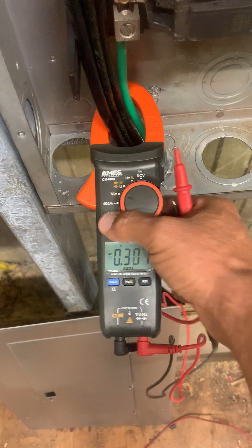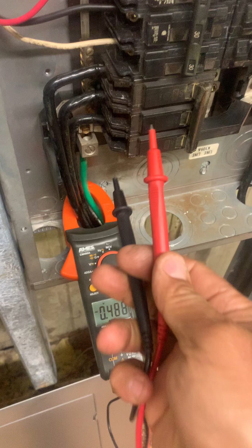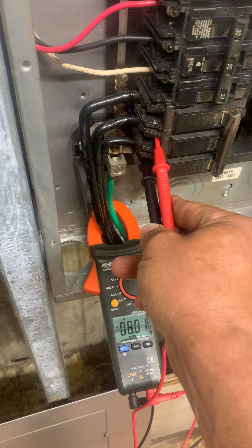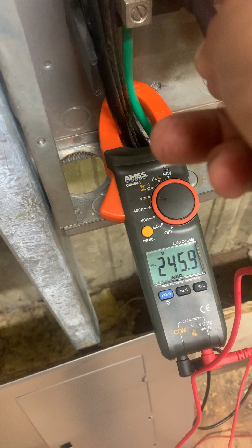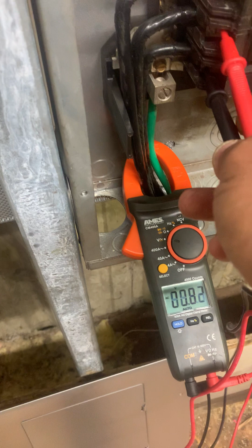I'm just gonna pinch in here, I'm doing nothing, just holding the meter. I'm gonna put it on voltage, select my power range, and hopefully I don't get shot here. This is my first two legs, 1 and 2, so A and B. I'm at 246.9, 246, 245.9, somewhere over there. That's my 1 and 2 leg reading.